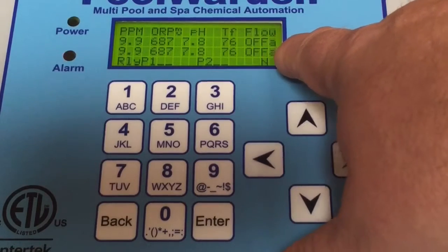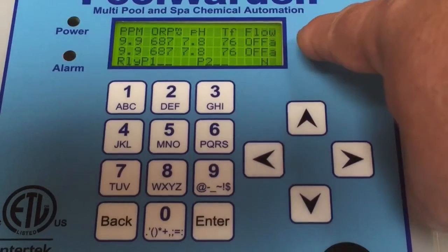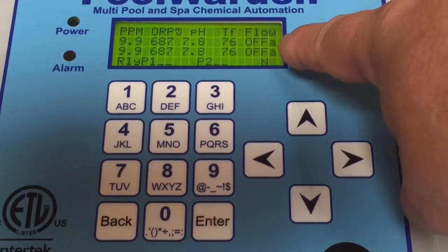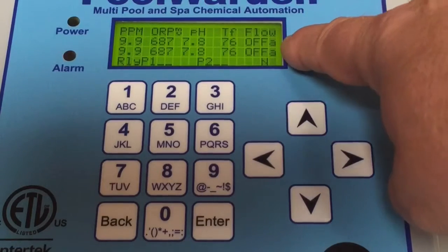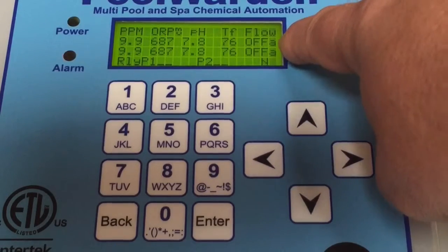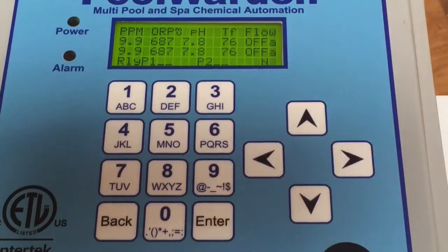On flow, these are both off because this is a demo unit, but normally these would read on, meaning there is flow through the bypass and it will allow it to feed chemicals. If this says off, it cannot feed chemical. Next to this, you have an A for alarm.